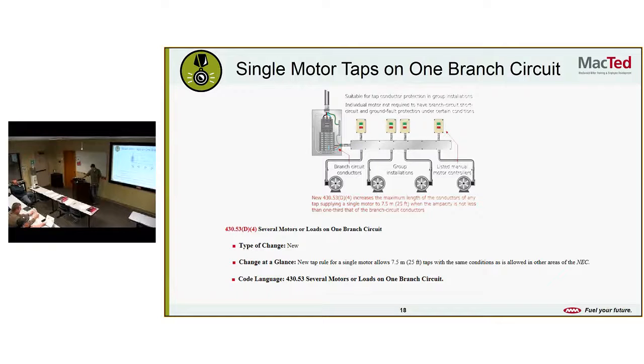All right, single motor taps on one branch circuit. There's a new type of code change here. New tap rule for single motor allows 7.5 meters or 25 foot taps with the same conditions as allowed in other areas of the NEC. Several motor loads or loads on one branch circuit. So they've increased the maximum length of the conductors of any one tap. So now you have a little bit more leeway if you're putting motors on circuits.